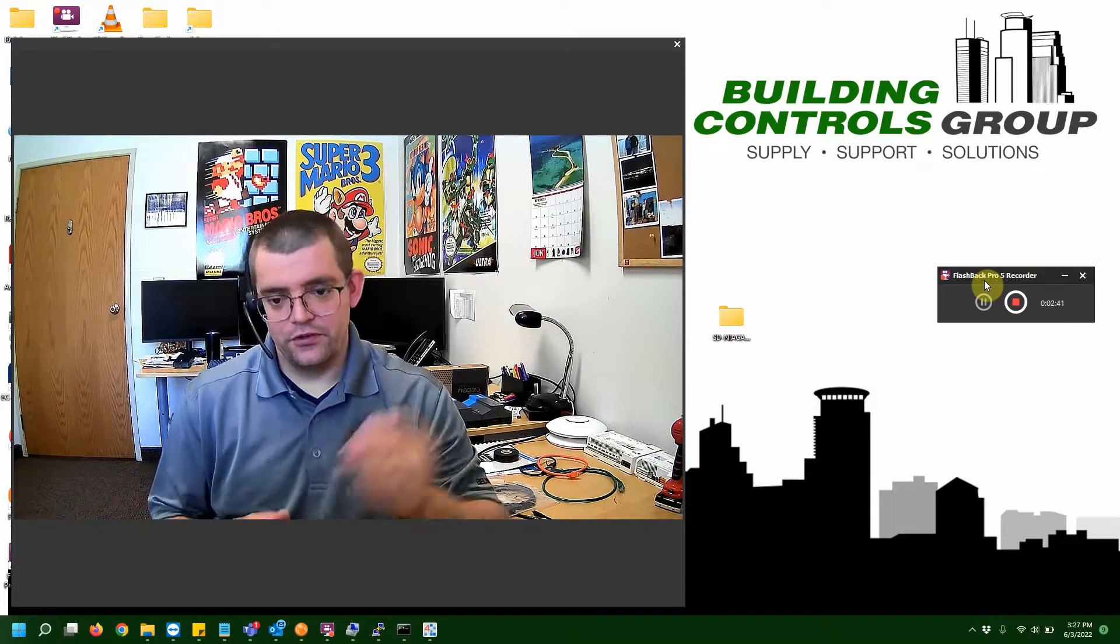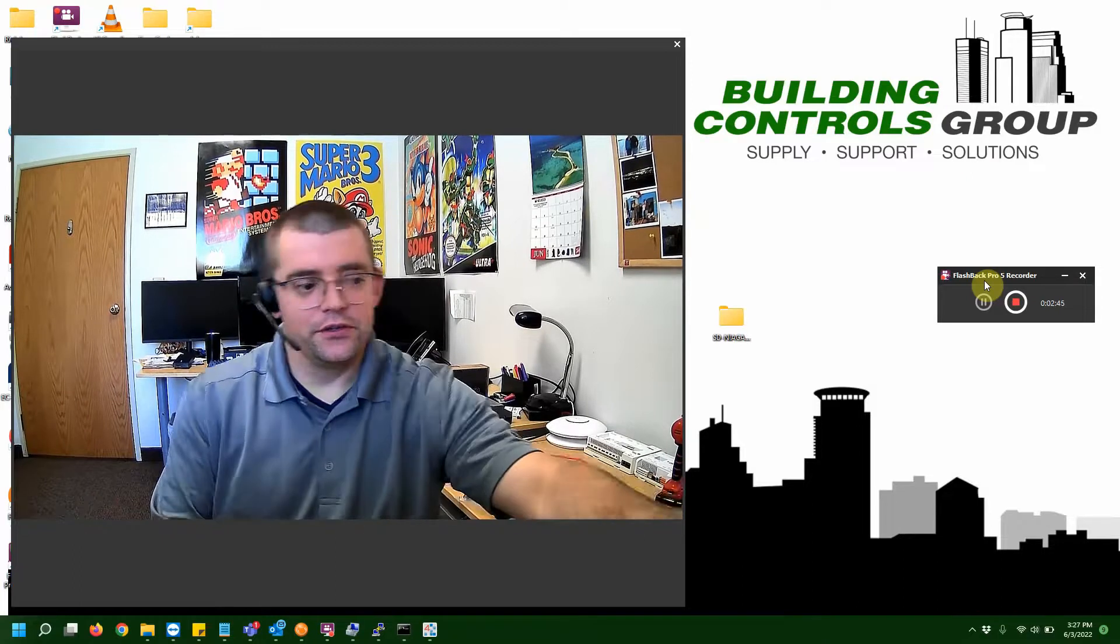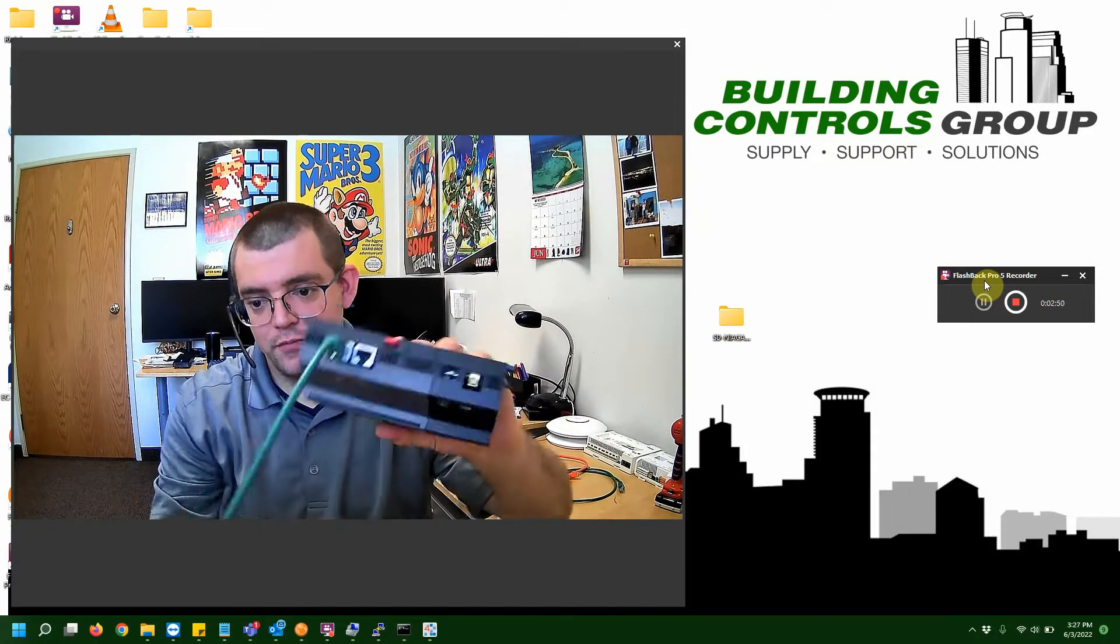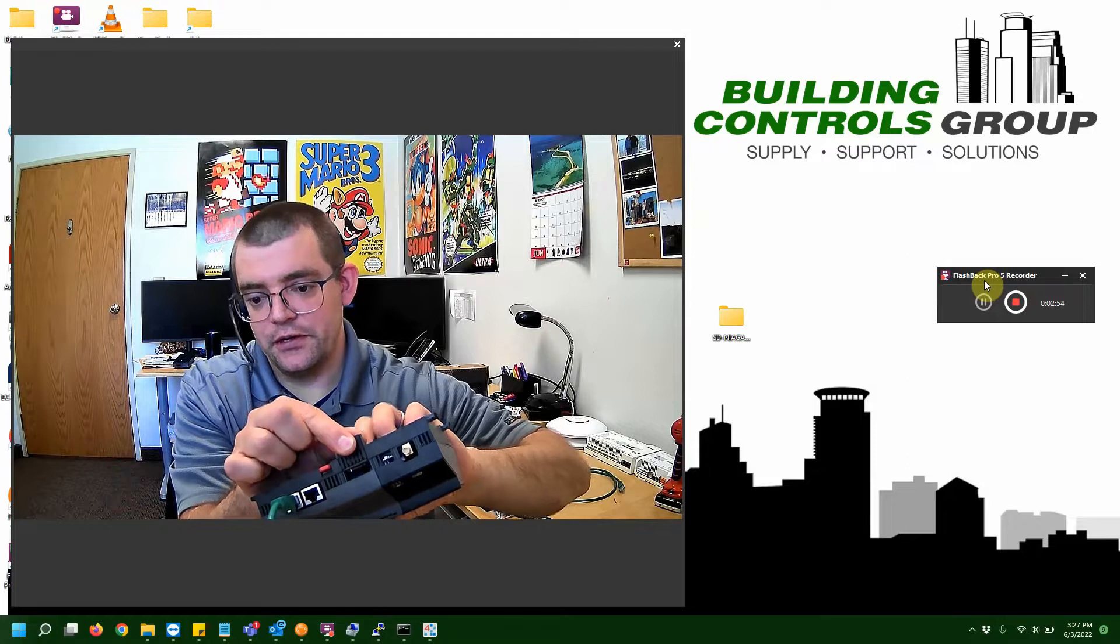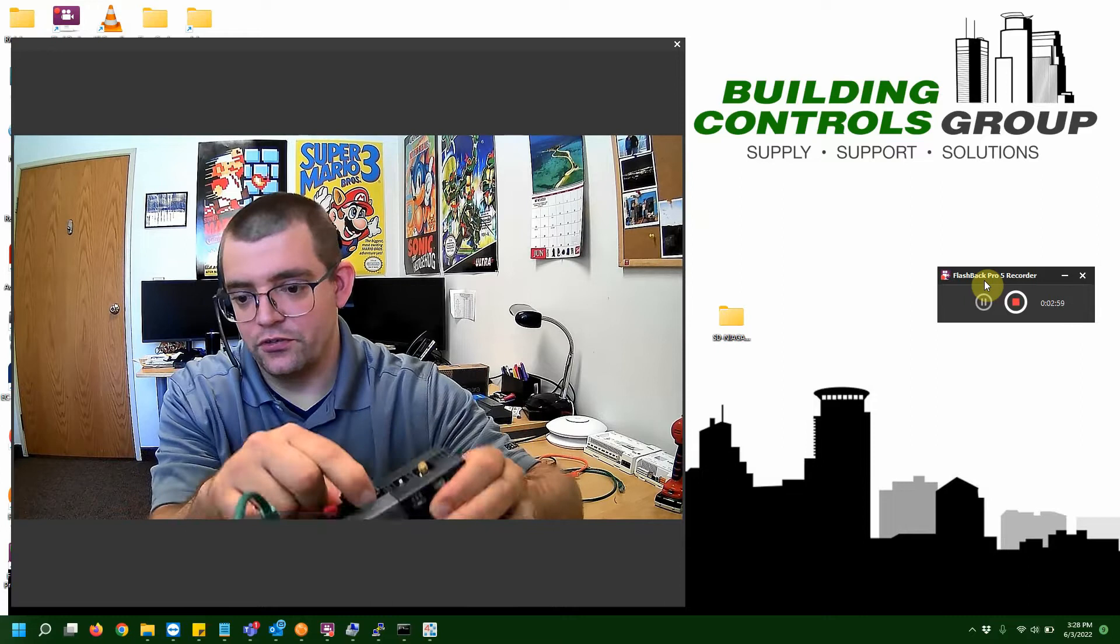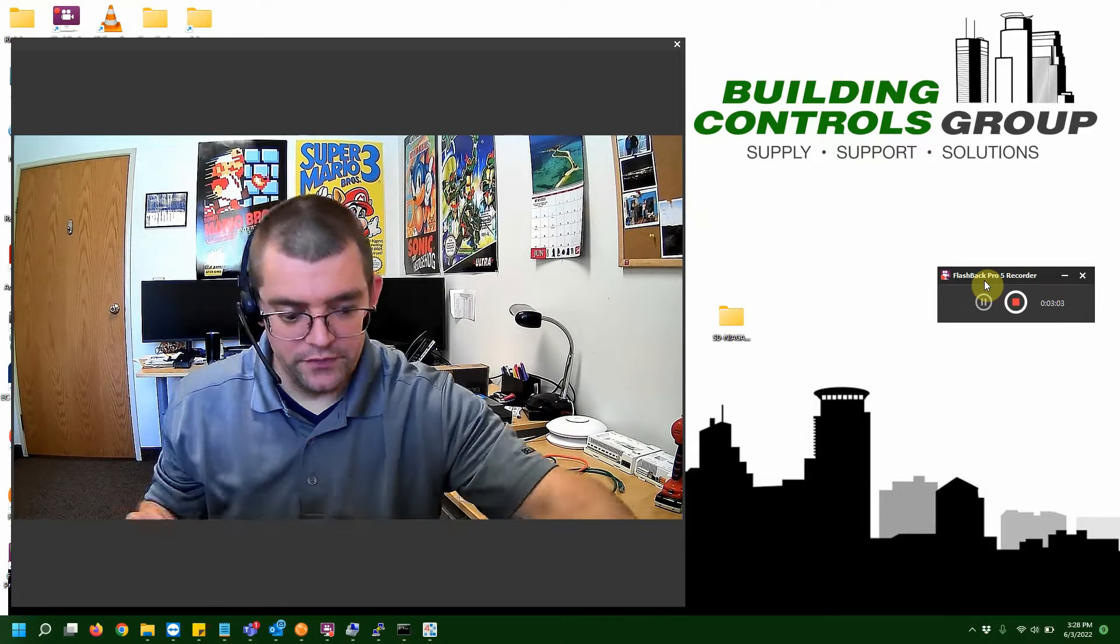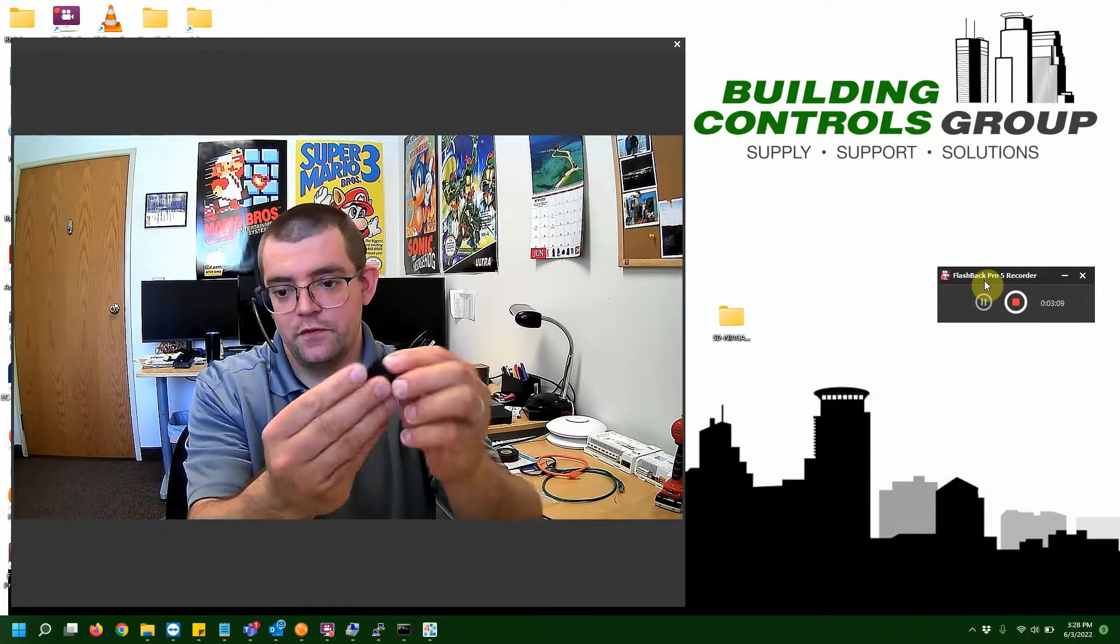First what we're going to do is we're actually going to pop the Jace off my DIN rail here. And we're going to open up the slot. On the bottom of every Jace, it's always the same. There's this little guy right here and it just slides open. And if you look in there, you can just barely see the SD card. We're going to just push in and it pops out. We're going to set the Jace down for right now. And for me, I'm going to plug this into my SD card adapter. And then I am going to plug that into my laptop.